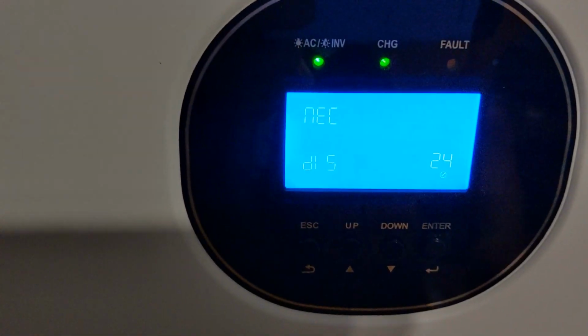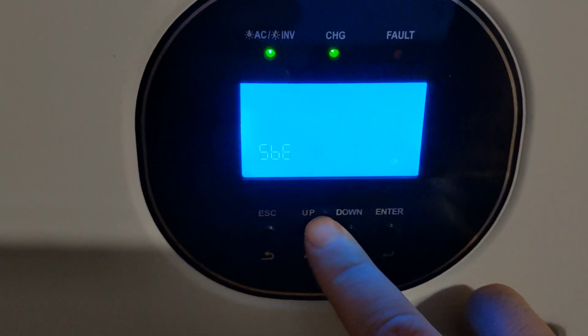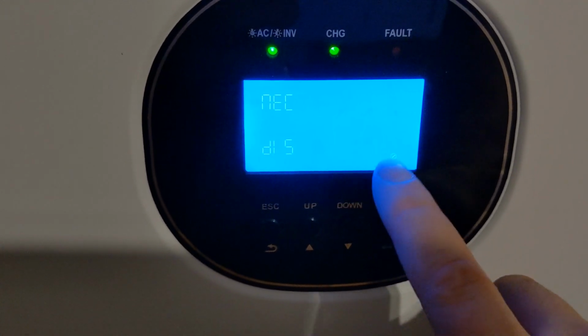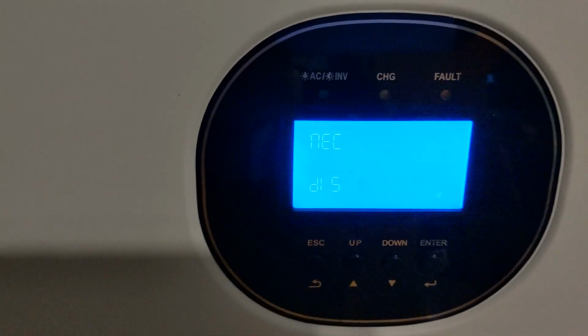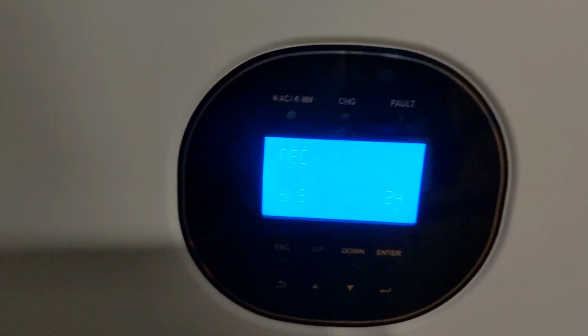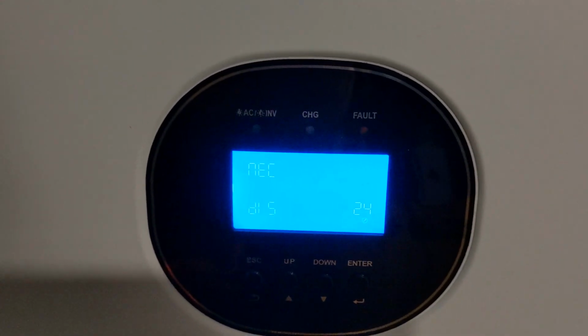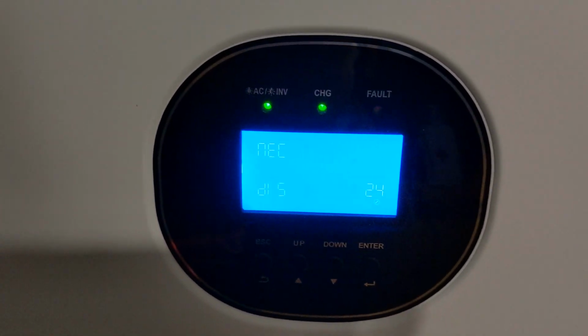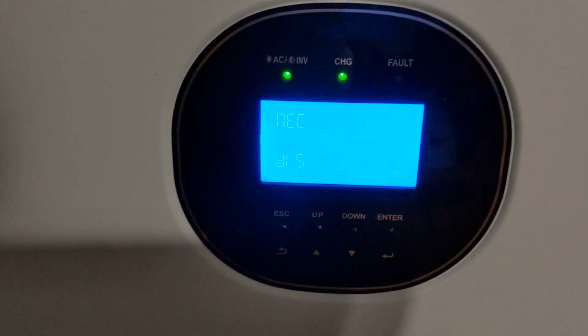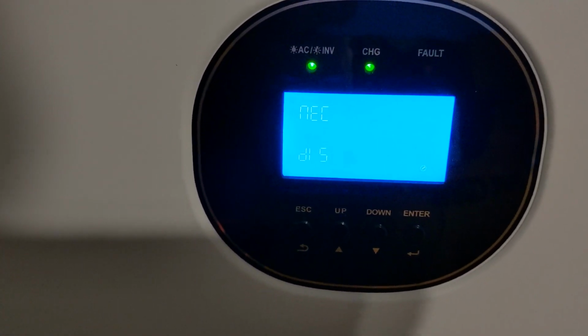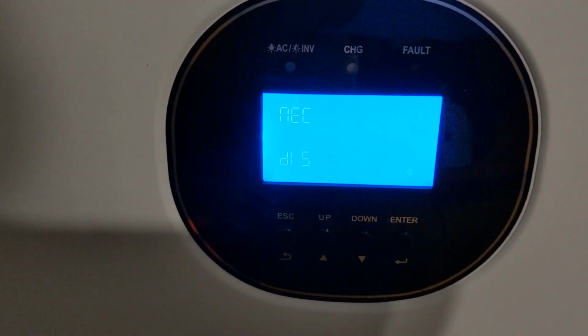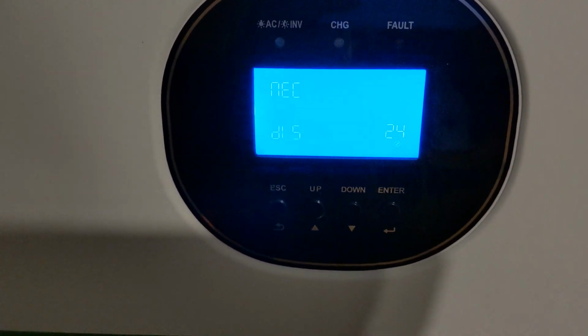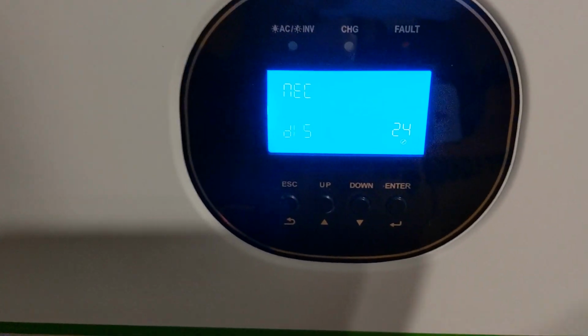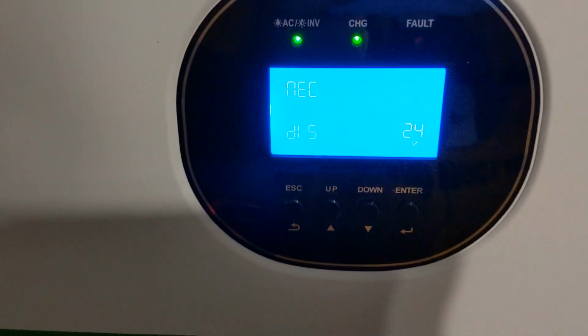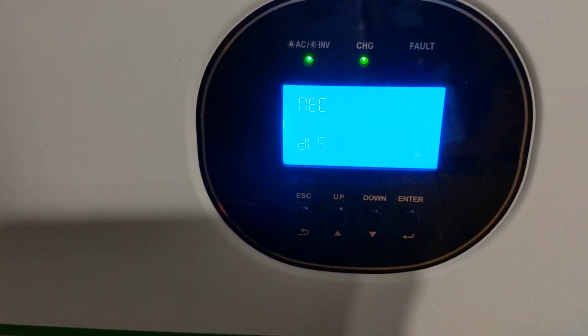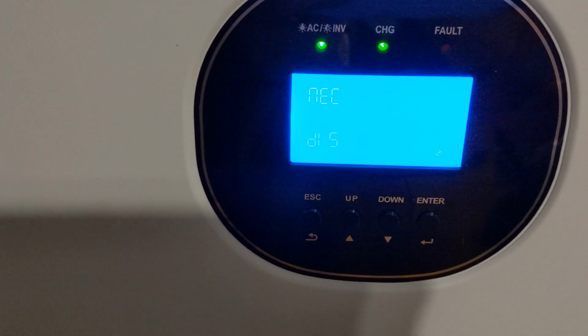The reason you notice that it skips over those two numbers, 22 and 24, is that number 23 is where you set the power output of these units. So if you have multiple units paralleled together, or if you have them set up in split phase mode, that's where you set the settings for that. There are different phases that you can choose under 23. Obviously, if you changed that while it was on, very bad things could happen to all of your electronics, so they only let you change that when the inverter is off.